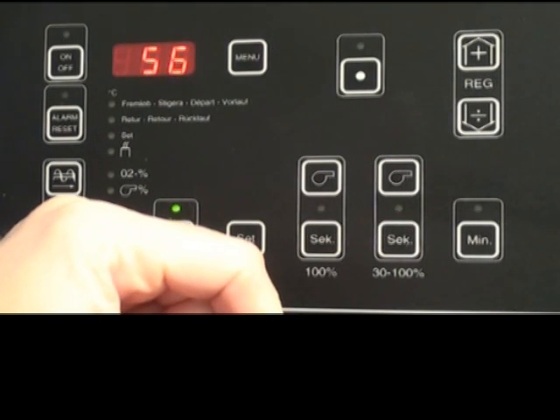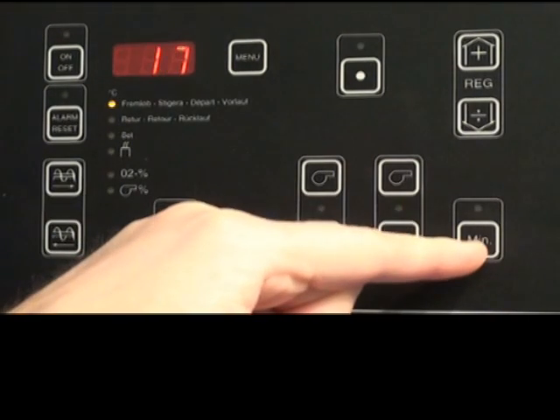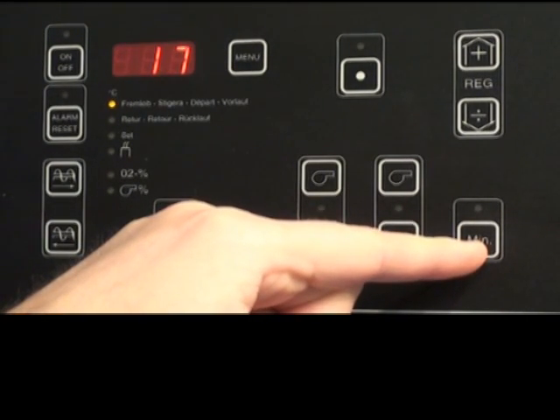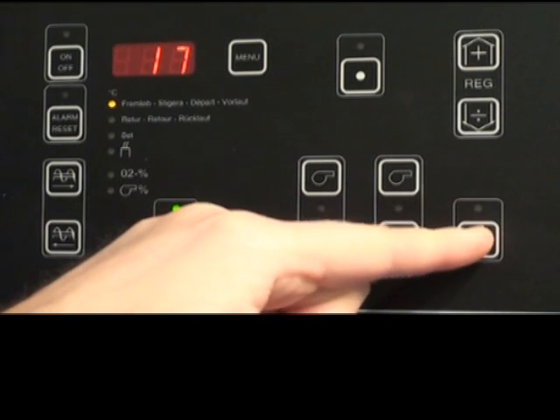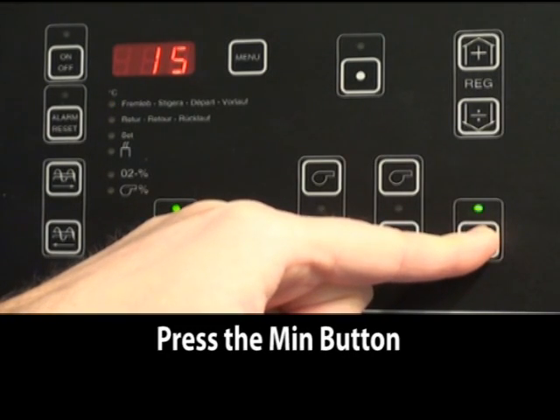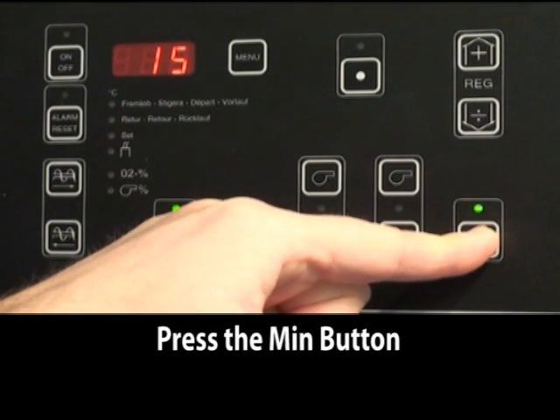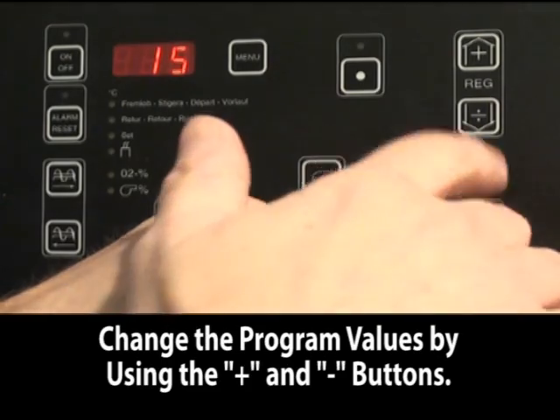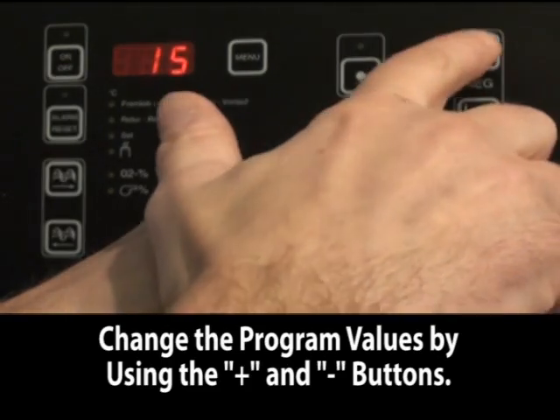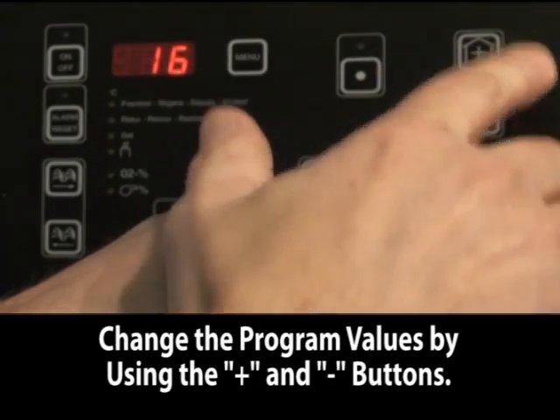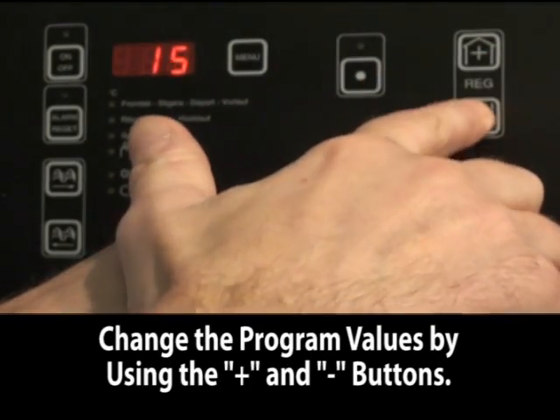The last thing to check is the min setting, or basically the time it sits in standby. It should be set to 15 minutes, and this is for all boilers. If you need to change, use the plus or minus button.